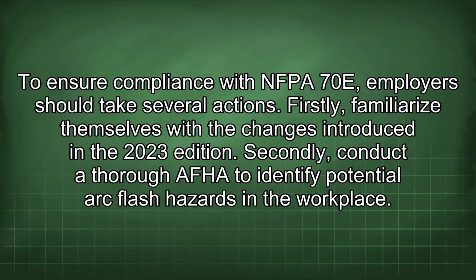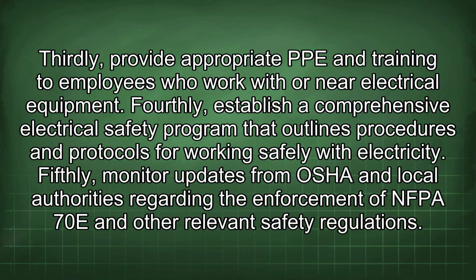To ensure compliance with NFPA 70E, employers should take several actions. Firstly, familiarize themselves with the changes introduced in the 2023 edition. Secondly, conduct a thorough AFHA to identify potential arc flash hazards in the workplace. Thirdly, provide appropriate PPE and training to employees who work with or near electrical equipment. Fourthly, establish a comprehensive electrical safety program that outlines procedures and protocols for working safely with electricity. Fifthly, monitor updates from OSHA and local authorities regarding the enforcement of NFPA 70E and other relevant safety regulations.